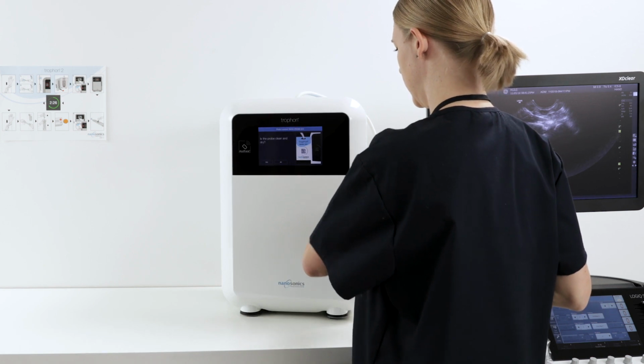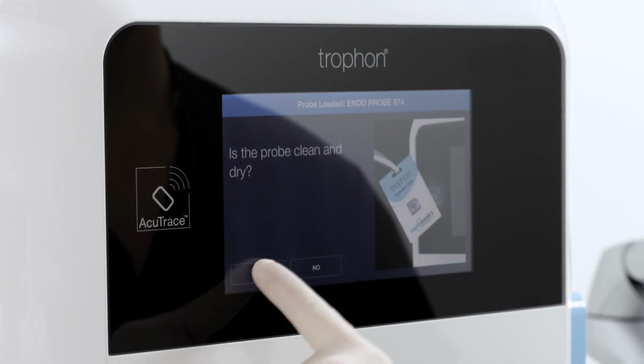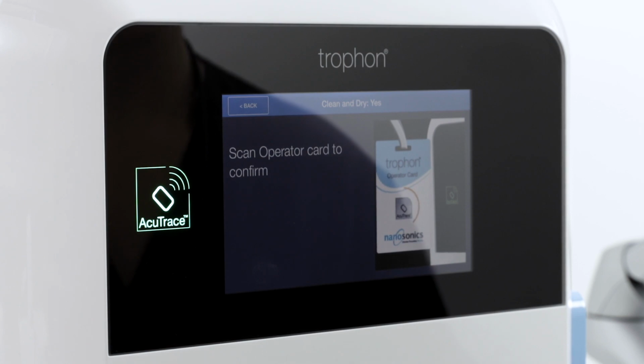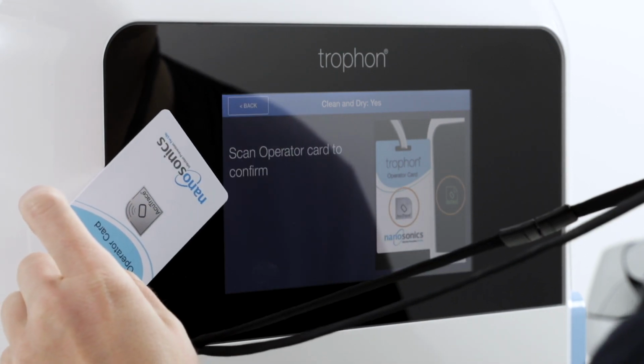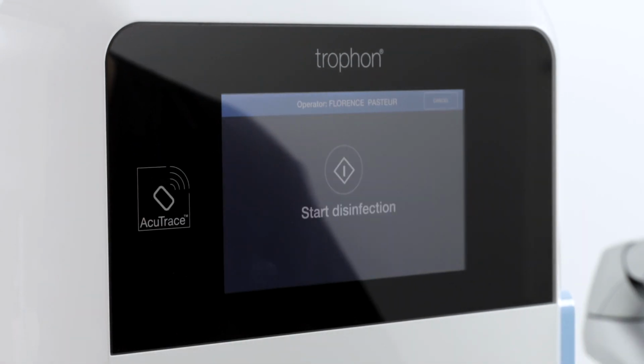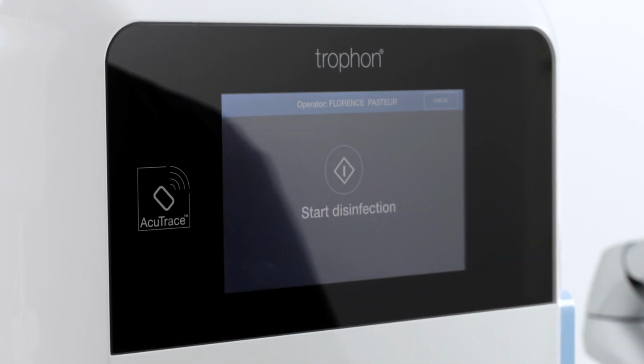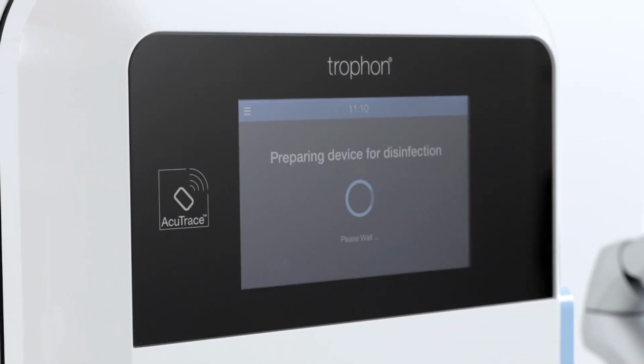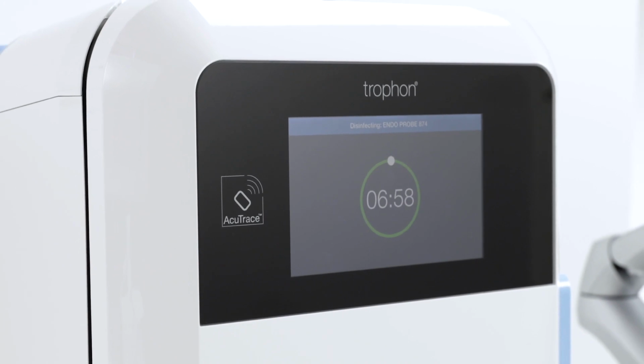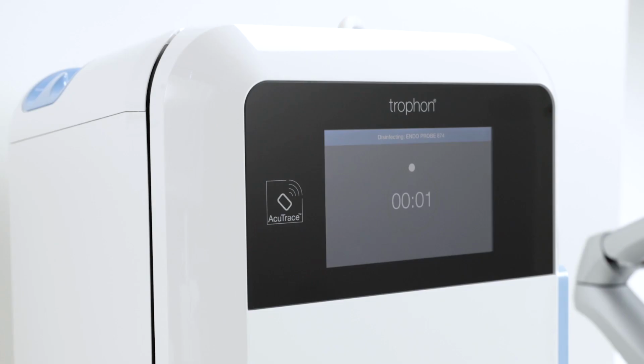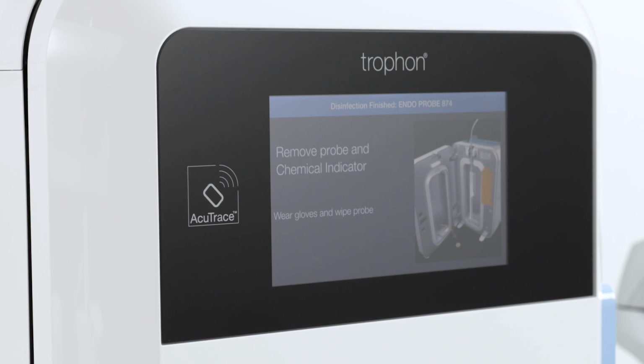Verify that the probe is both clean and dry by selecting Yes on the trophon2 screen. Confirm by tapping your operator card against the Acu Trace reader. Press the Start button. The chamber door will stay locked during the 7-minute disinfection cycle. At the end of the high-level disinfection cycle, trophon2 will beep once to indicate the cycle is complete.